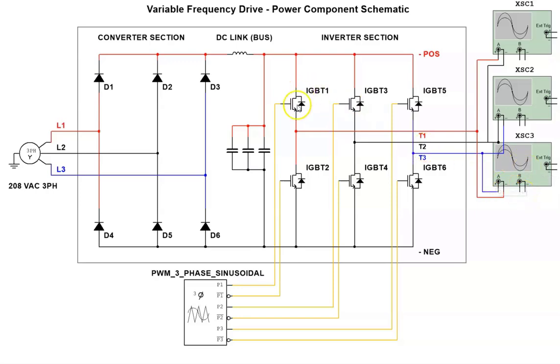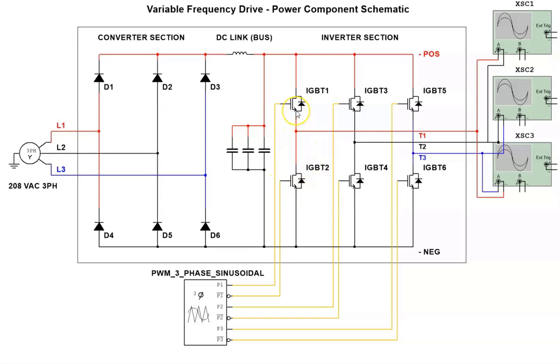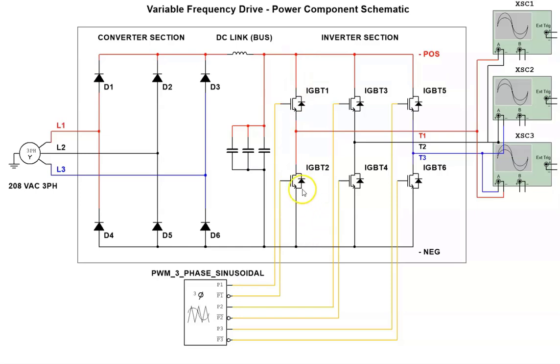Now in the inverter section we have three sets of transistors and they work together. IGBT1 and IGBT2 are tied together. The emitter on transistor 1 connects to the collector on transistor 2. If both of these transistors were on at the same time you would have a short across the DC bus and you would have some serious issues going on. So we have a controller that only allows one of them to be on at any given time. And as a matter of fact, if one is on the other is off. They're always toggling. Just think of transistor 1 and transistor 2 toggling on and off.